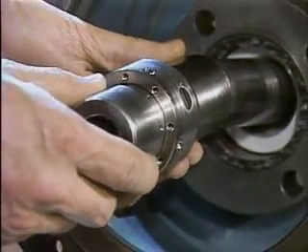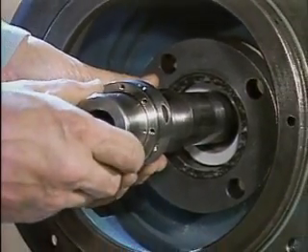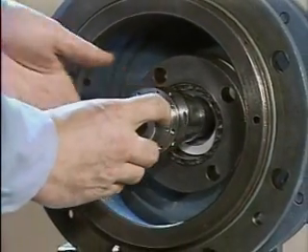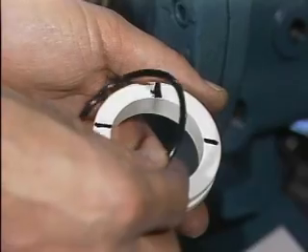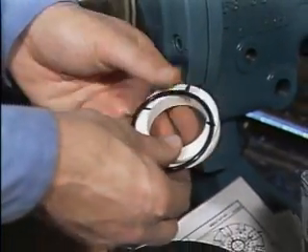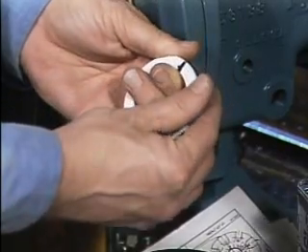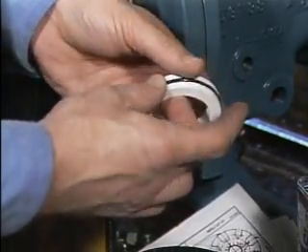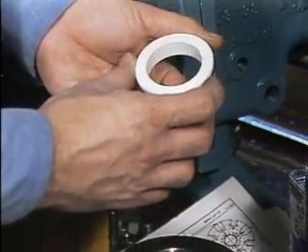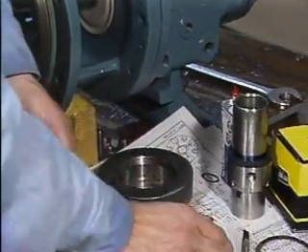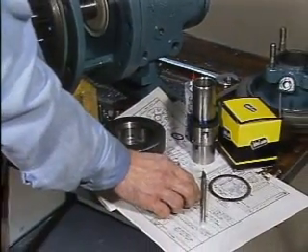The seal faces are among the easiest components to damage by mishandling because they're usually quite brittle. However, some mechanical seal components can be damaged because they're relatively soft. For example, during installations, O-rings or bellows are sometimes cut by sharp edges on the shaft, such as shaft shoulders or shaft keyways.